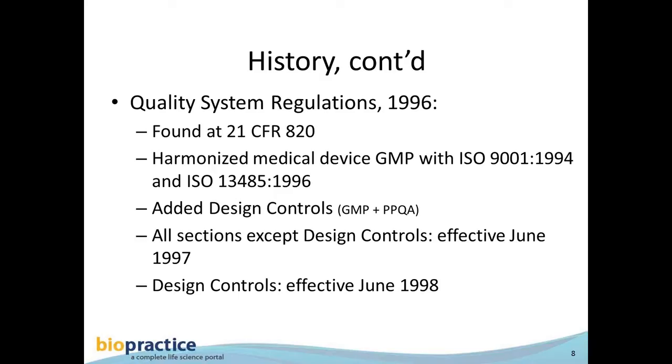Previously, the Safe Medical Devices Act of 1990 had talked about pre-production quality assurance. That's an acronym, PPQA. So the Quality System Regulations in 1996 combined GMP regs with pre-production quality assurance and gave it the title design controls.